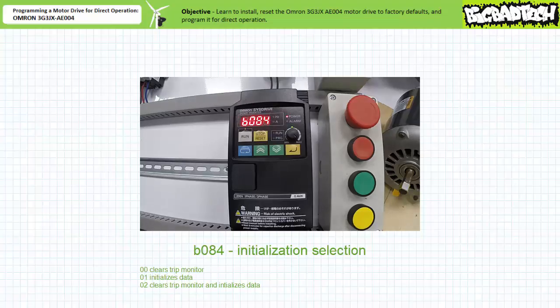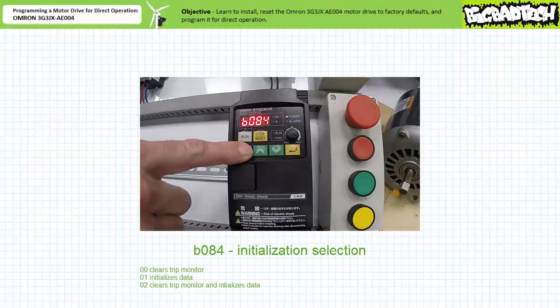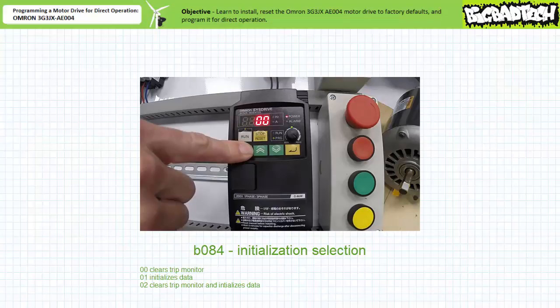I press mode again to read the current entry. Note the drive is currently in state 00, and the program LED is lit, indicating that I can change this entry. If we want to both clear any previous errors and initialize this drive to the factory default, I increment this parameter to 02.